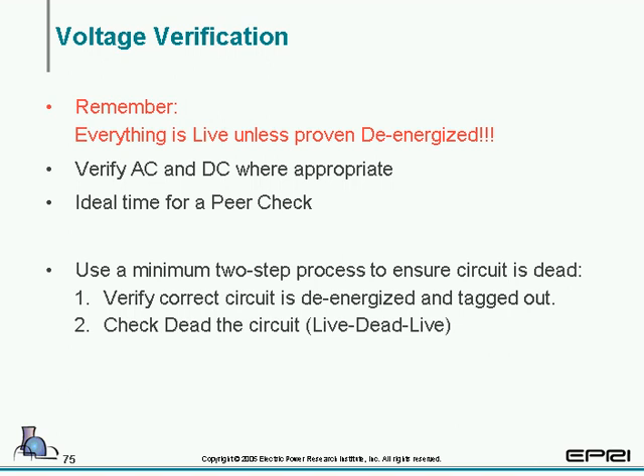This is an ideal time for peer check. You can verify both AC and DC. You could use a minimum of two-step process to ensure the circuit is dead. Verify correct circuit is de-energized and tagged out, and use dead live checks.